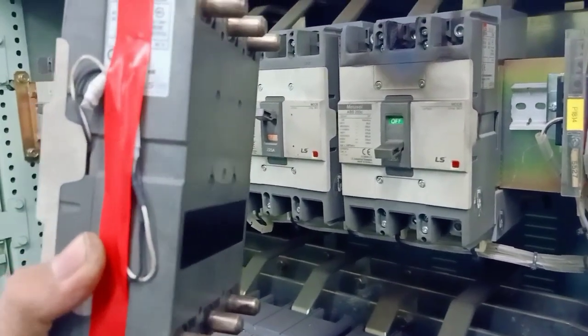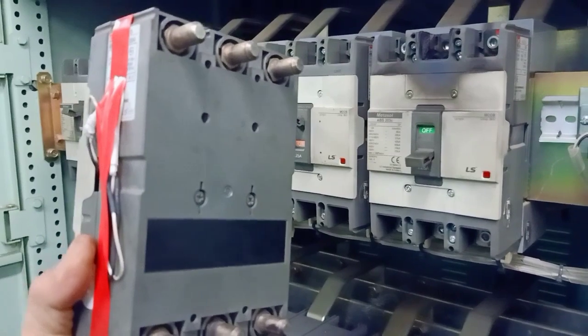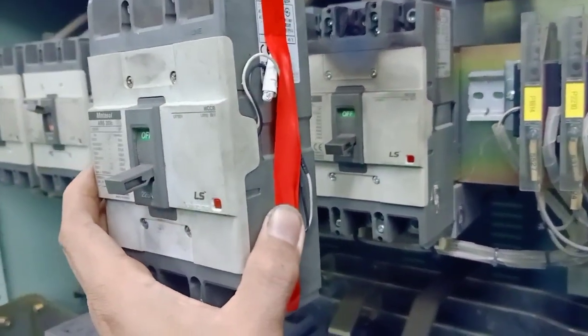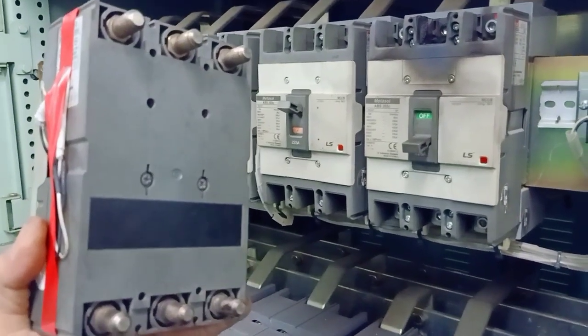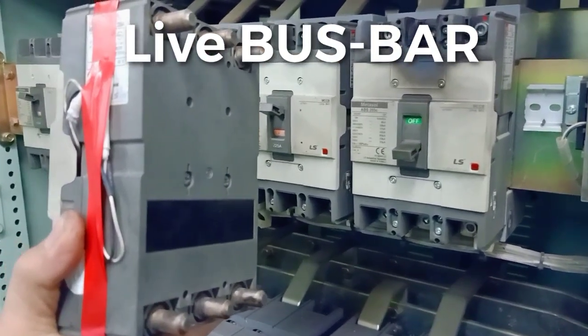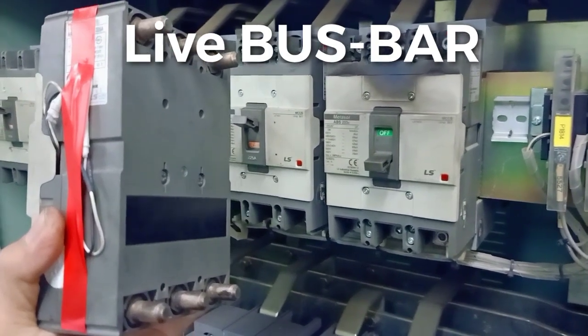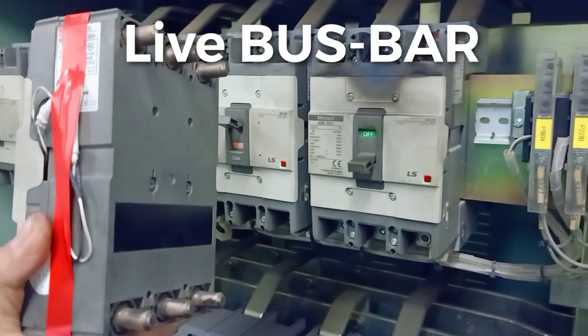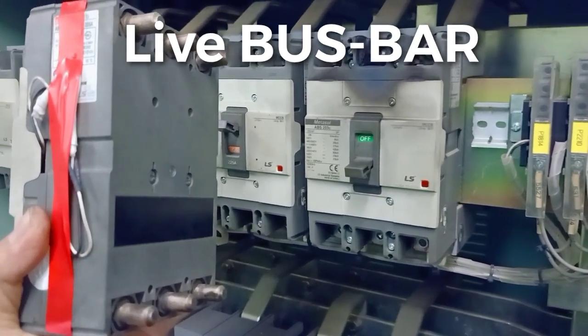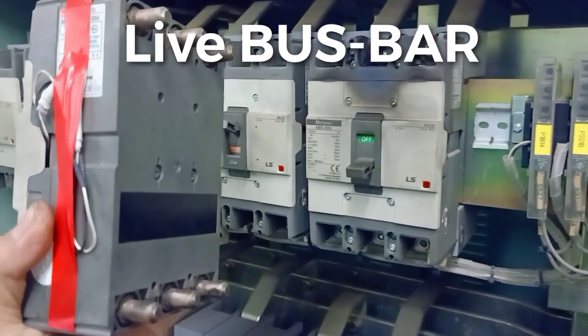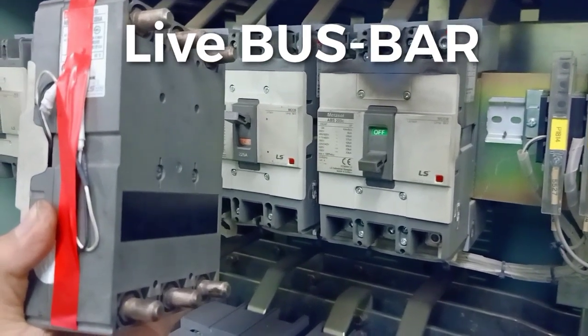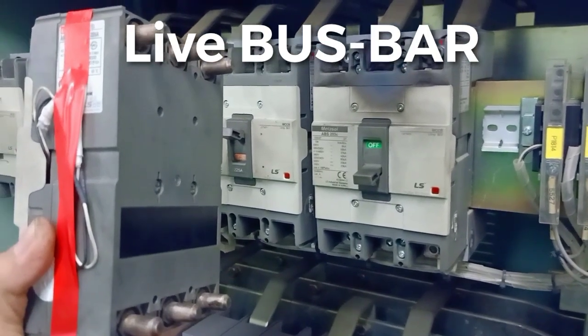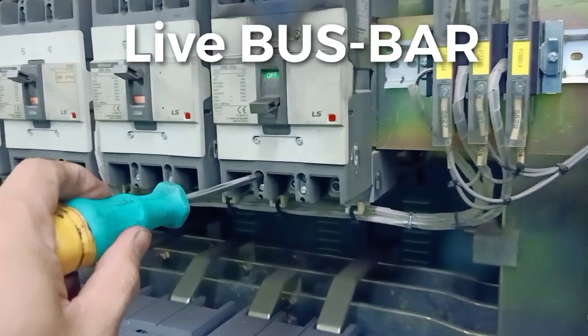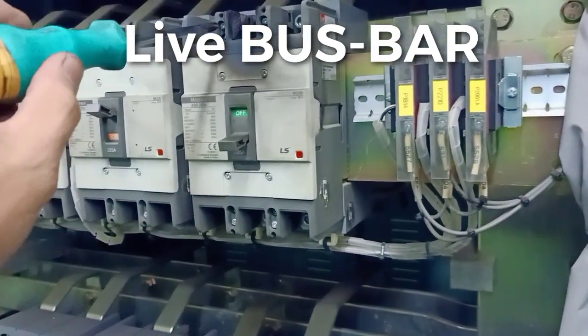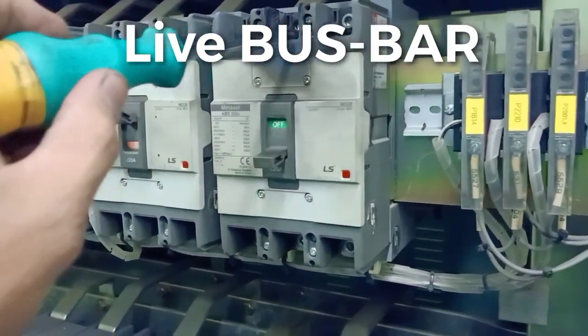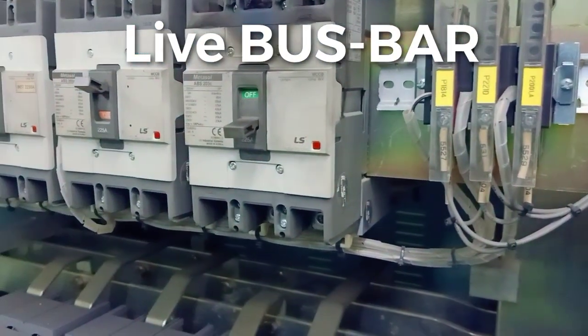This kind of circuit breaker going to the main switchboard is a plug and pull. This is it. I'm going to remove the circuit breaker even if it is live, because we need all the machinery working, as we are about to berth, so we don't have any more time. To remove, we have 4 screws, 1, 2, 3, and 4. After, pull this breaker.